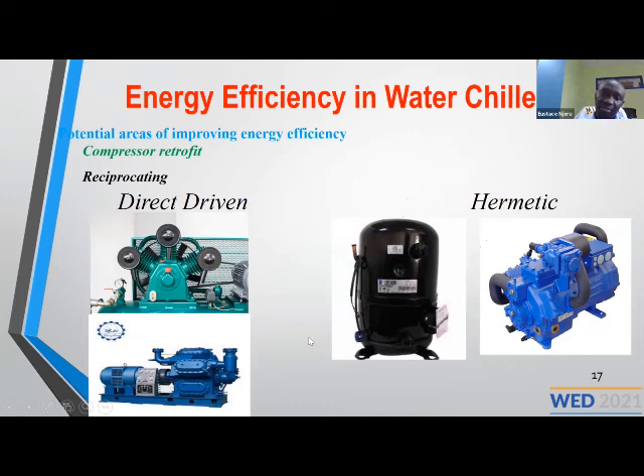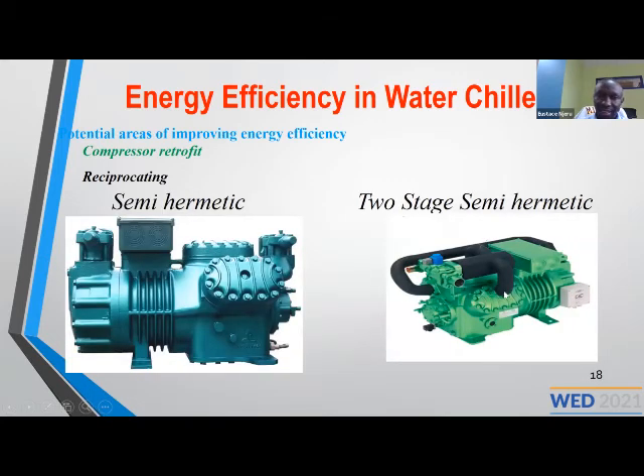So these ones are used in small units of water chillers. These are direct driven. They are not hermetic, but they are less efficient compared to hermetic. So if you are using small units, you had better use hermetic than direct driven. Avoid the direct driven as much as possible. We have semi-hermetic. If you go to relatively bigger water chillers, you can use the semi-hermetic.